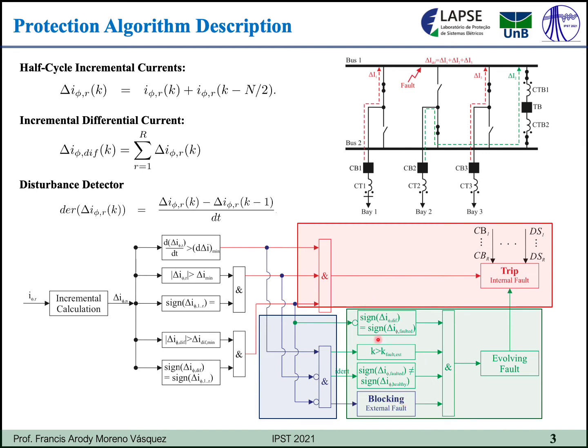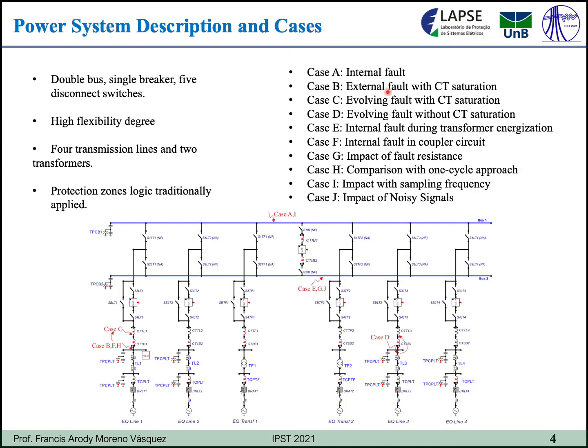Nevertheless, we can experience the evolution of an external fault into an internal fault, and in this case, it was identified that there is a change in the polarity of the differential current, and it acquires the same polarity as the initially faulted feeder. And if this event occurs, if the polarity of the differential current changes, we will have an internal fault, and in this case, we must send the trip for internal fault. So, in order to test the proposed method, several cases were performed, as shown in this list, and all of these results I fully explain in the paper corresponding to this work.